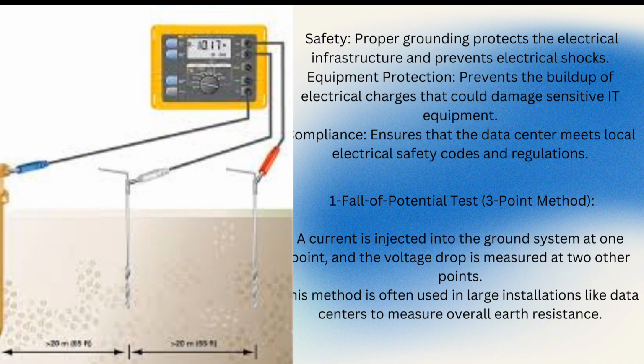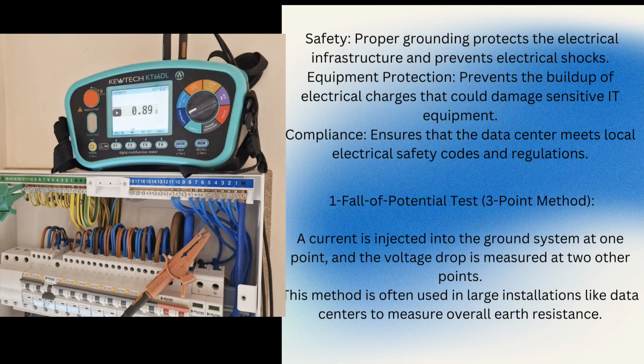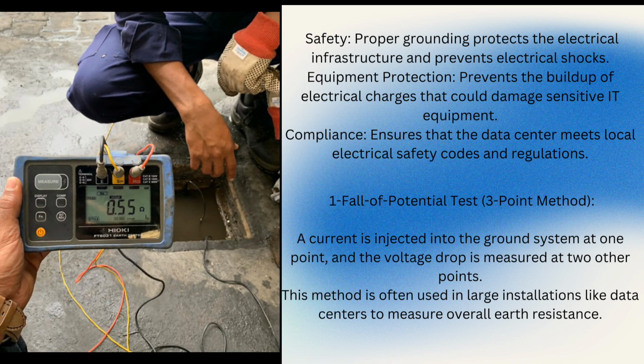Common earth testing methods: first, the fall of potential test, also known as the 3-point method. A current is injected into the ground system at one point, and the voltage drop is measured at two other points. This method is often used in large installations like data centers to measure overall earth resistance.